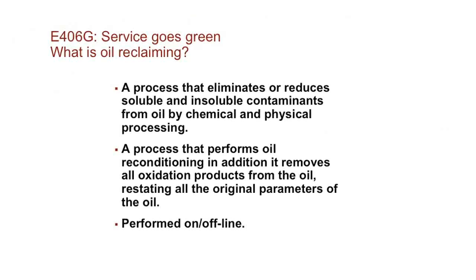So what is reclaiming? Just to give a general idea of oil reclamation. Reclamation is we eliminate or reduce the soluble and insoluble materials that are in the fluid. So any sludge, moisture, contamination that the fluid has accepted over time and deteriorated, the cellulose as it breaks down, we can remove that material from the insulating fluid and return it back to refinery grade material.